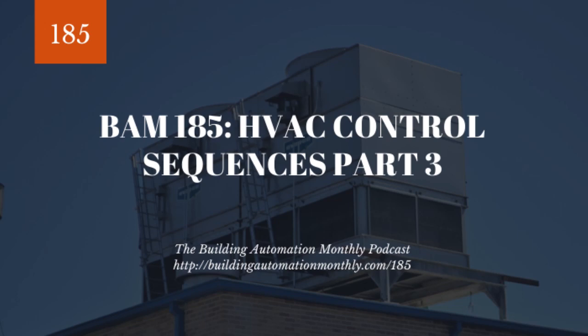Now, when we talk about economizer, we have various different ways of controlling it, but in a nutshell, economizer serves two purposes. Economizer serves a free cooling purpose, which is if our outdoor air is at a certain point, either via temperature or via temperature and humidity, enthalpy, if we are looking at the temperature of the air, or we're looking at the energy in the air, which is moisture content. I'm going to take a brief segue to talk about that because there's a lot of folks who don't understand psychrometrics and they don't understand moisture content in air and what that means. So I really want to go down that path with you real quick.